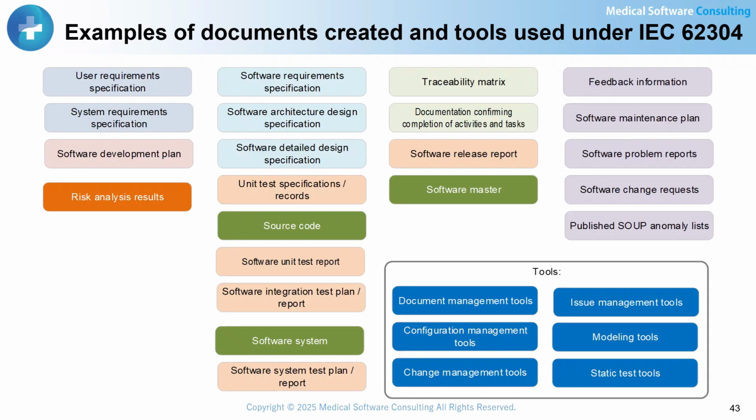Here are examples of documents created and tools used under IEC 62304. To demonstrate compliance with IEC 62304, it is necessary to prepare these documents and deliverables. As for tools, in practice you will need document management tools, issue tracking tools, configuration management tools, change management tools, modeling tools, static test tools. When such tools can affect the quality of a medical device, they must be validated as QMS software in accordance with the requirements of ISO 13485.